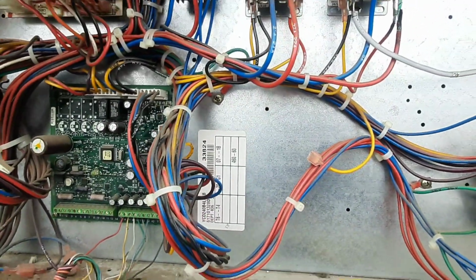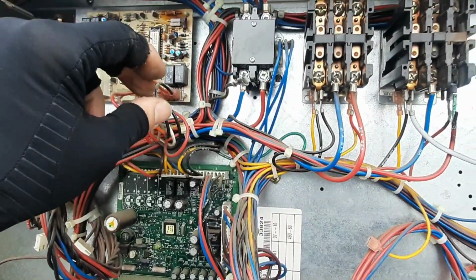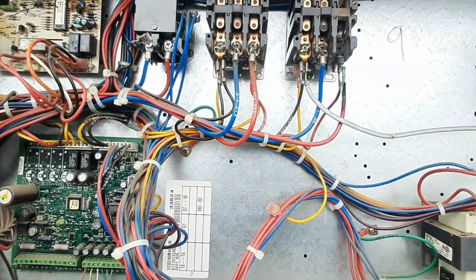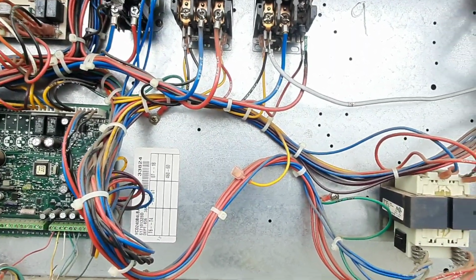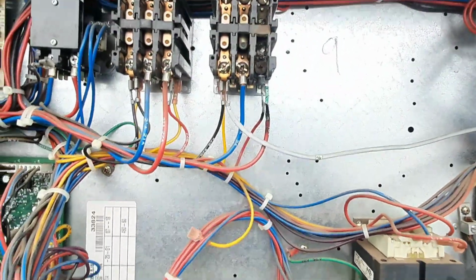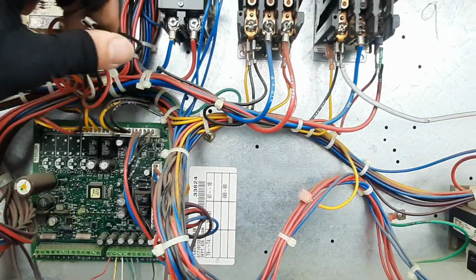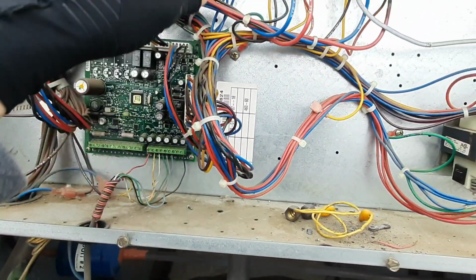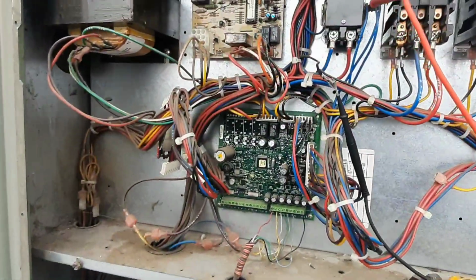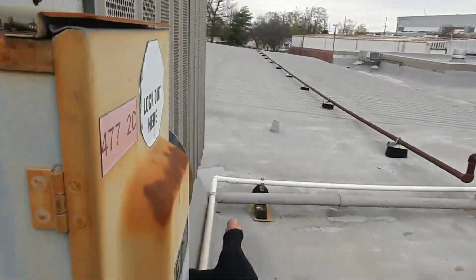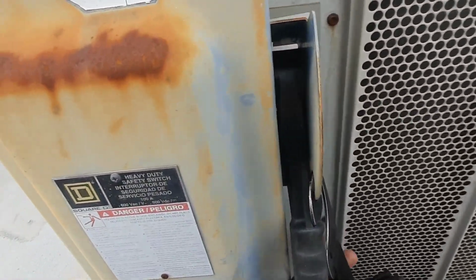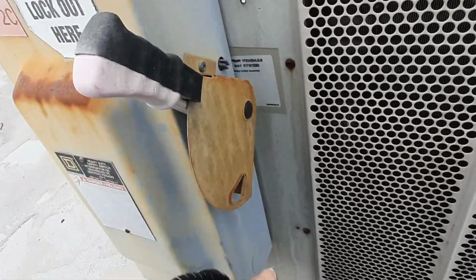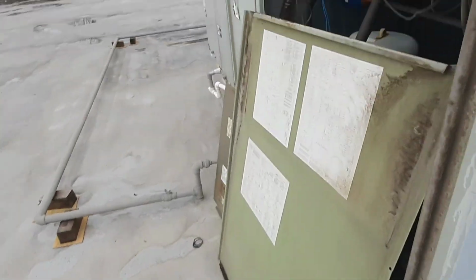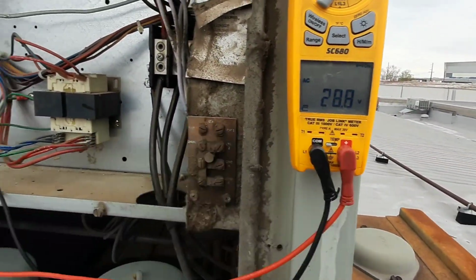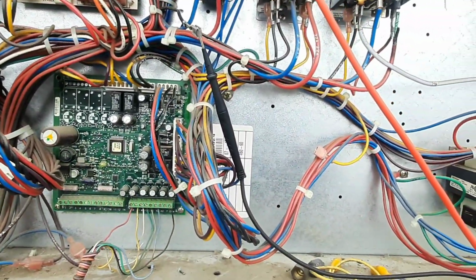Just make sure the contactor coil isn't dropping us out or anything, so we'll get hooked up here, see if I've got a good signal. Don't know why. I don't know, we'll kick it back on in a minute and see what happens. We did go ahead and pull my Y1 or 2, whatever the hell that is. Let's check here and see why the fan call that I don't have low voltage coming in is dropping out. Now there was no lockout on my heating board, so I think that's going to be okay. Let's kick it back on. .28 volts. It's on my fan call.